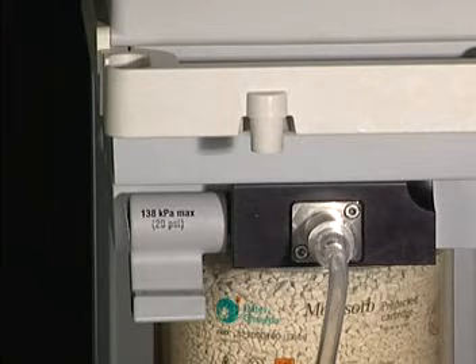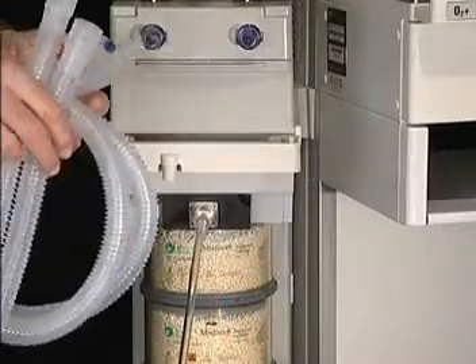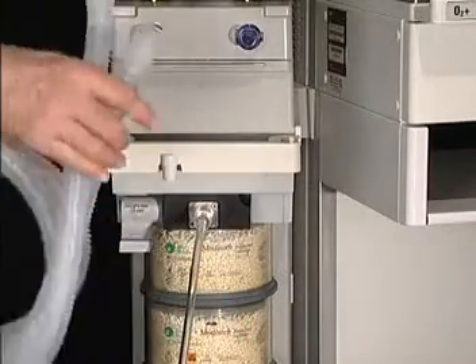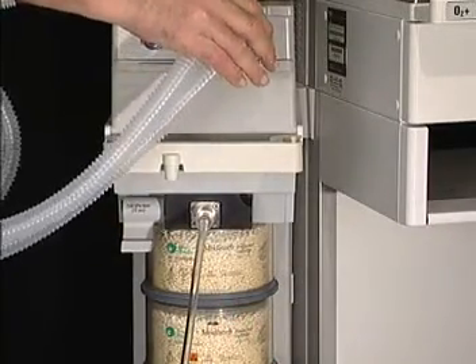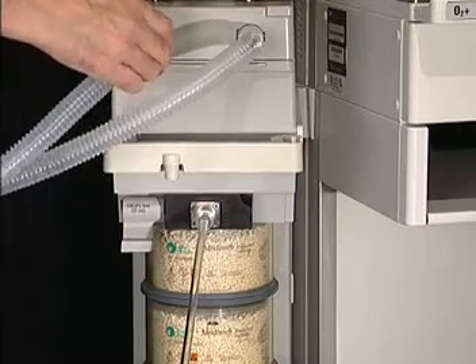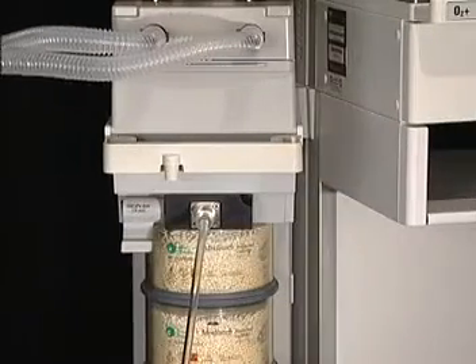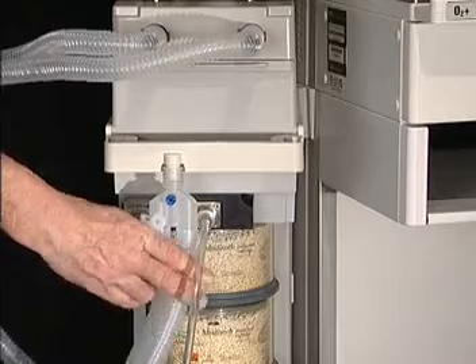This can lead to agent being expelled from the inspiratory port of the circle module into the work area. To prevent this, a circle circuit should be placed on the circle module, the APL opened, and the circuit Y piece plugged. The occluder built into the handle of the breathing system can be used as the plug.